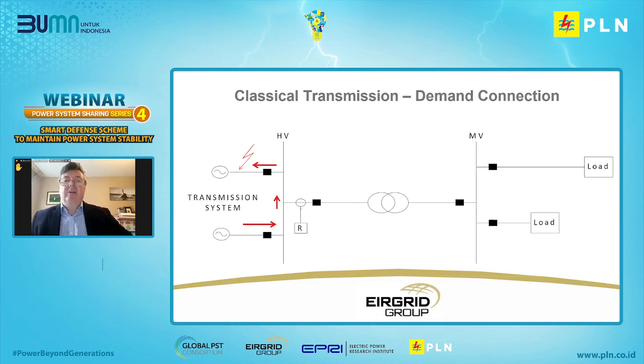Now, if we have a fault on the transmission system itself, the sources of power or short circuit are from some other part of the system. So there's no contribution from the distribution system where there's no generation connected. So move on to the next slide, please.